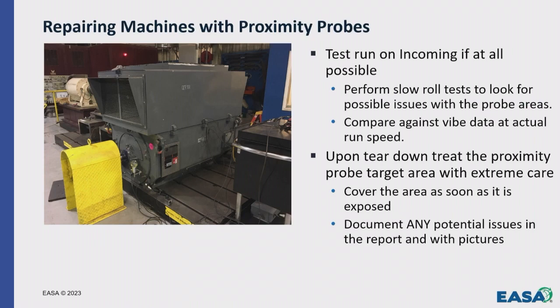So when it comes to repairing machines with proximity probes, like anything else on larger or medium-sized machines, test run it on incoming if possible. Most of your vibration equipment will connect to the drivers inside of the prox cabinets. Most of your customers send in the entire unit. If they don't, you can ask for it. But test run on incoming and do a slow roll. Most of the standards out there call a slow roll around 300 RPM.